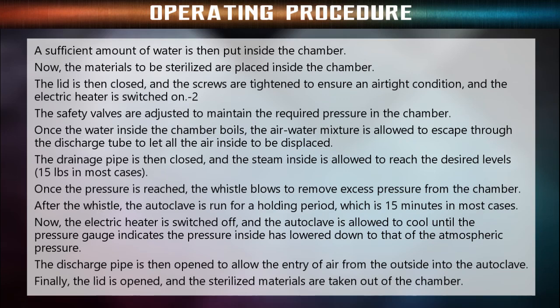The following are the steps to be followed while running an autoclave. Before beginning to use the autoclave, it should be checked for any items left from the previous cycle. A sufficient amount of water is then put inside the chamber. Now the materials to be sterilized are placed inside the chamber. The lid is then closed and the screws are tightened to ensure an airtight condition, and the electric heater is switched on.